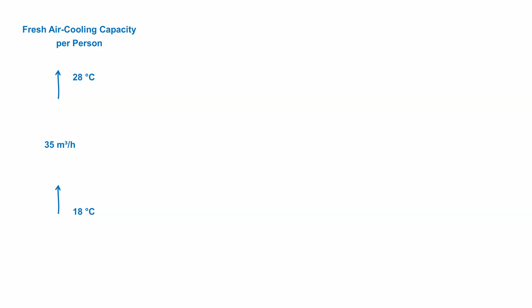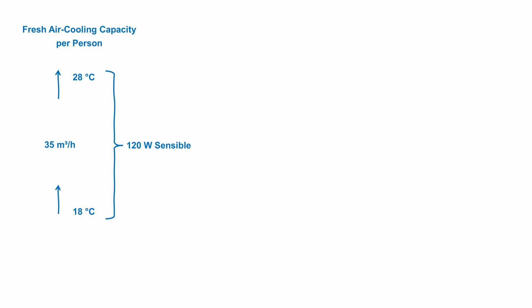Supplying each person with 35 cubic meters of temperate fresh air at 18 degrees already provides effective cooling. As this air warms up by 10 degrees from 18 to 28 degrees, this is equivalent to a sensible cooling capacity of about 120 watts. At typical light activities in a studio, a person produces also about 120 watts of total heat load. About 75 watt of that is sensible heat, about 45 watt is latent heat from perspiration.